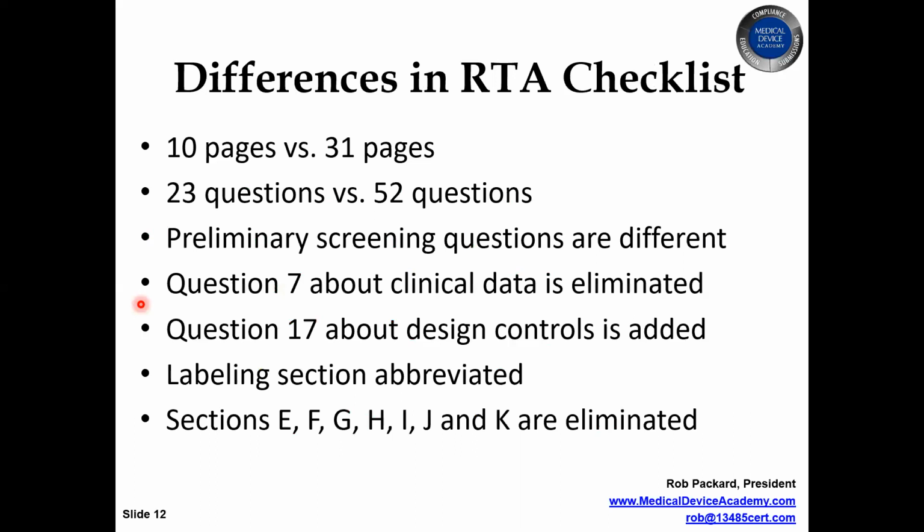Question 7 is completely eliminated in a special 510K because you can't submit new clinical data. If you need to submit new clinical data, that would typically be for an indication for use change, expanded indications, or major modifications. So no new clinical data, so they eliminate that question.